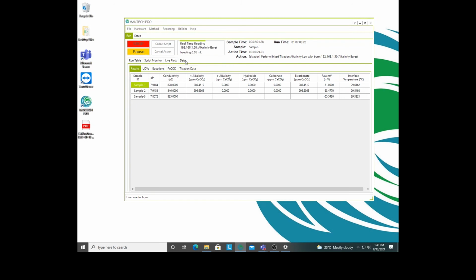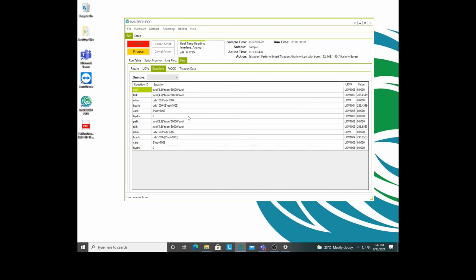We can go back here and look at our previous data that was acquired. So you have your pH, conductivity, and then your speciated alkalinity results. So you have the hydroxide, carbonate, bicarbonate on there as well. The millivolt readings on the electrode, temperature compensation for all of the pH readings. That can be done either from a USB connected thermistor or directly from a thermistor that's on the conductivity probe, depending where we're measuring the pH, really, or whichever parameter we are measuring. So yeah, it's pretty good like that. We can look at the equations that it's using even here. So you can see exactly how it's getting each one of the results.